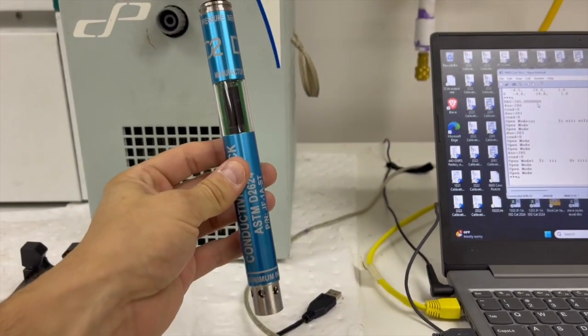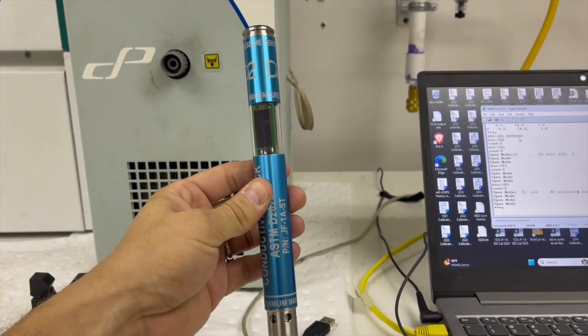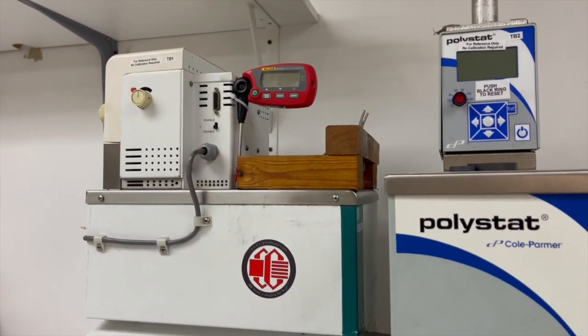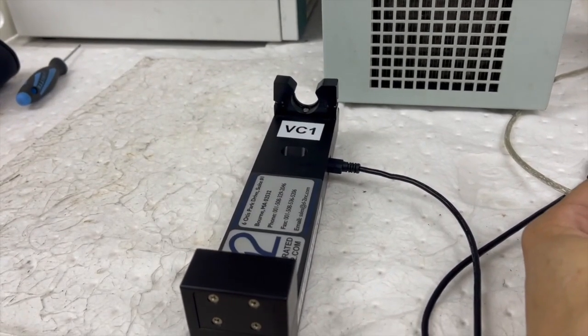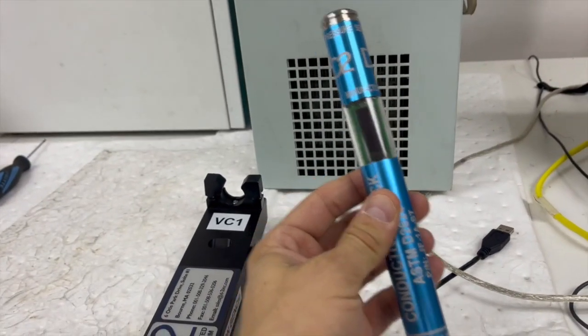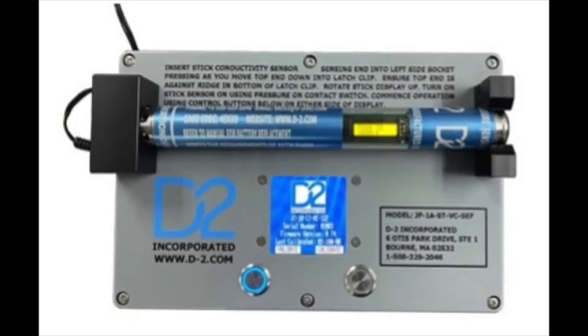Welcome to a video where I'm going to be showing you how to use this, the JF-1A ST handheld conductivity meter, a temperature bath with a handheld temperature probe, our USB calibration for the stick, which can also be replaced by the SEF box. This is the preferred device that we will sell with the kits, which is the JF-1A STVC SEF, which is a box that, as you can see, the stick handheld plugs into, and the box itself runs through the calibration process with a 2-button, very easy to use system, and can also run the verification process.